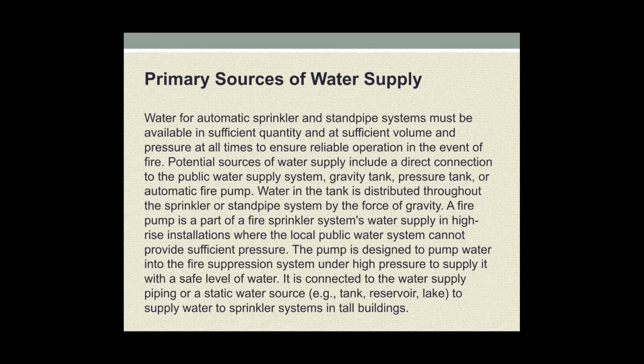A fire pump is a part of the fire sprinkler system water supply in high-rise installations where the local public water system cannot provide sufficient pressure. The pump is designed to pump water into the fire suppression system under high pressure to supply it with a safe level of water. It is connected to the water supply piping or static water sources to supply water to sprinkler systems in tall buildings.